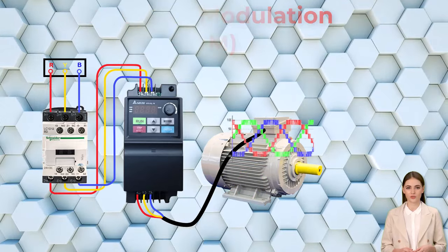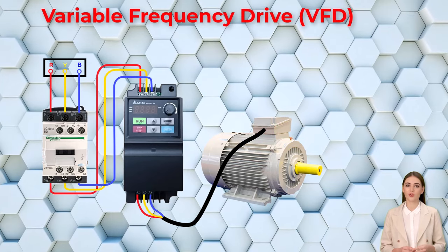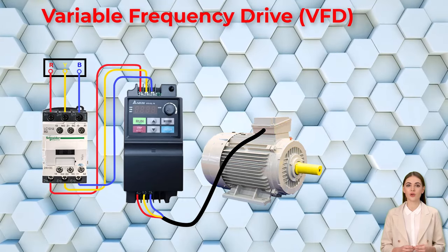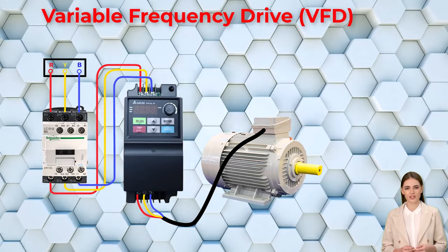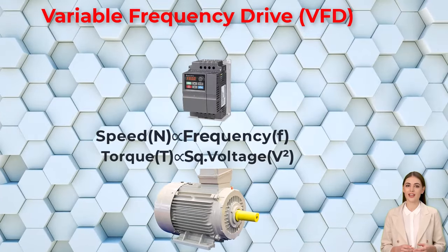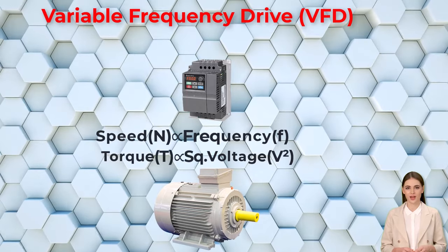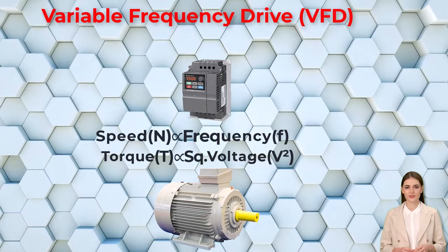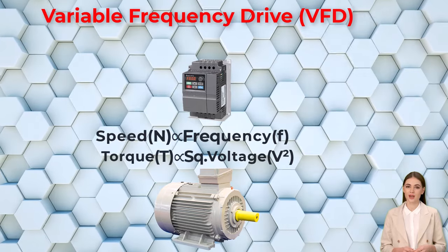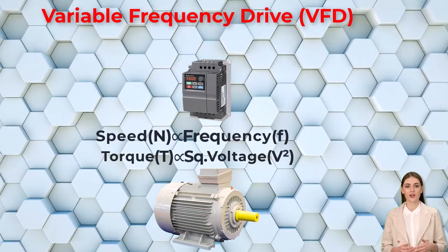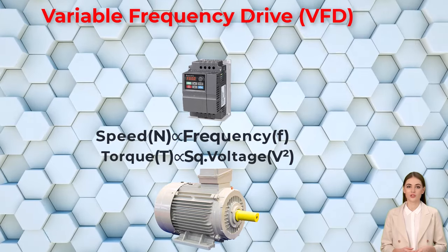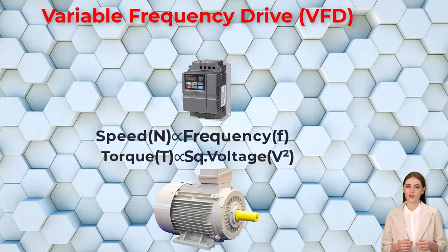This AC power is supplied to the motor, where it interacts with the motor's magnetic fields to generate torque and rotation. The frequency of the AC power determines the motor's speed, and the voltage determines the torque. The speed of an induction motor is directly proportional to the supply frequency, and the torque is directly proportional to the square of the supply voltage. By varying the frequency and voltage, a VFD can precisely regulate the motor's speed and torque, making VFDs ideal for applications requiring variable speed control.